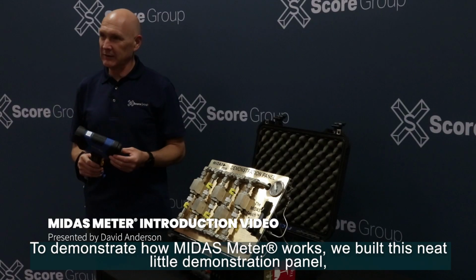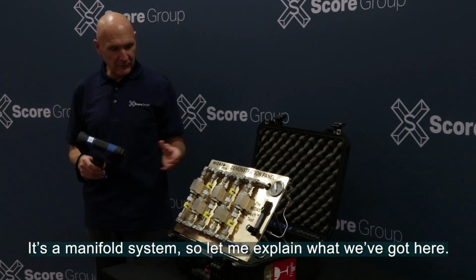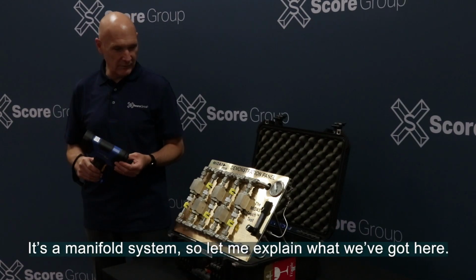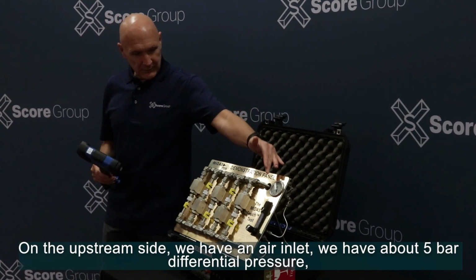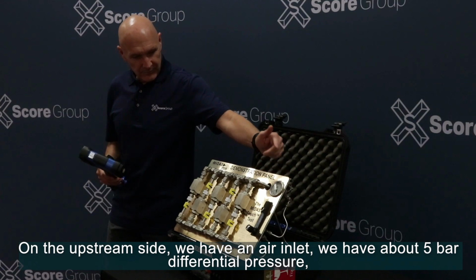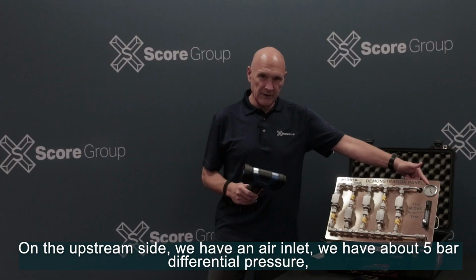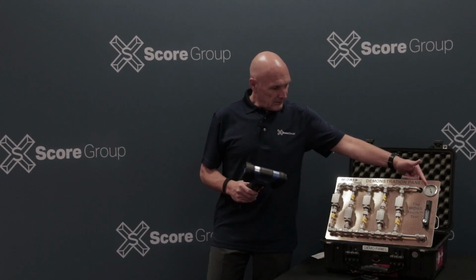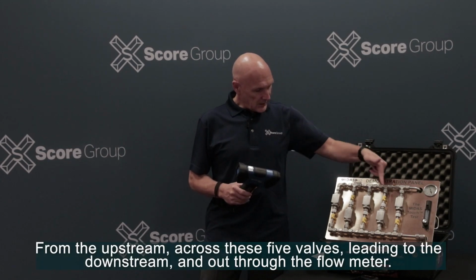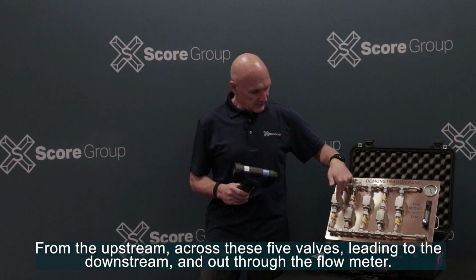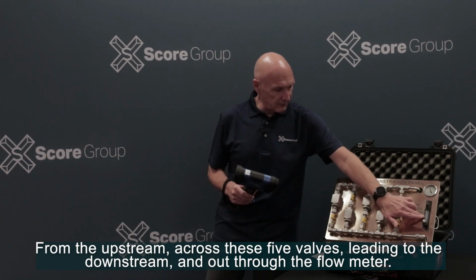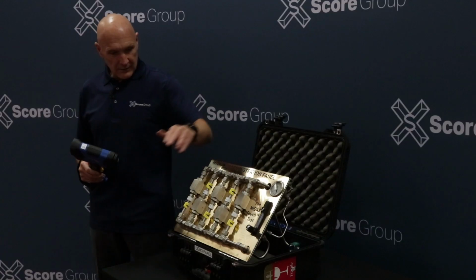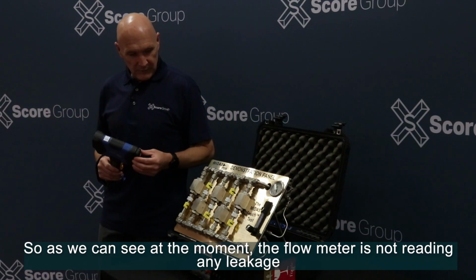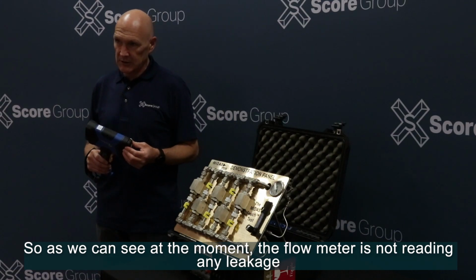To demonstrate how MIDAS meter works, we built this neat little demonstration panel. It's a manifold system, so let me explain what we've got here. On the upstream side, we have an air inlet. We have about 5 bar differential pressure. From the upstream, across these 5 valves, leading to the downstream and out through the flow meter. So as we can see at the moment, the flow meter is not reading any leakage.